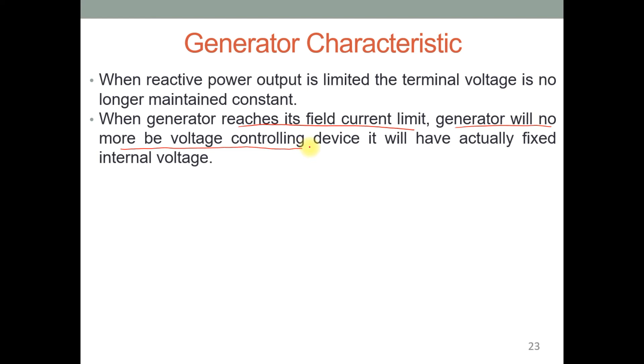Let us understand the flow. If the load demand is increased, that will affect the generator terminal voltage. It decreases, or we can say Q is increased. So to improve this voltage, the AVR comes into the picture, where the field current and armature current are increased up to a certain limit to improve the generator terminal voltage. Clear? So if we reach the maximum limit of IF or IA, then we are not in a position to control the generator terminal voltage, and hence the generator will act as a constant voltage source. Clear?